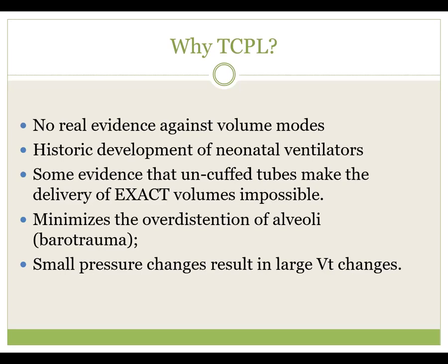We also have to account for uncuffed endotracheal tubes. In infants, we do not use cuffed tubes. We use uncuffed tubes, so there may be, or usually is, a leak. If we're trying to volume ventilate, we need to compensate for that leak.